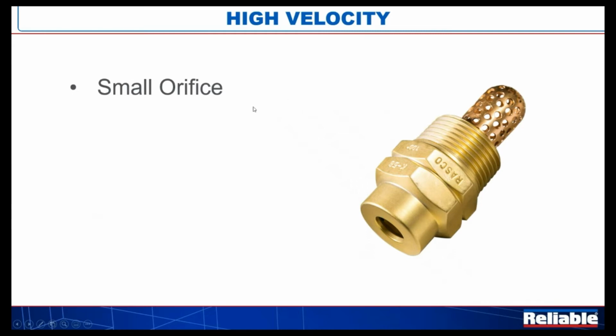They're going to have half-inch threads, but the orifice and the bore and the taper and contour of the bore up through the nozzle itself is going to be relatively small. You're typically going to see individual strainers mounted on these, depending on the K factor. And if they're too small, you may need a mainline strainer installed on the system as well. So small orifice number one, high velocity, high pressure. Typically, you're going to see these in maybe the 60 psi to 100 psi range.